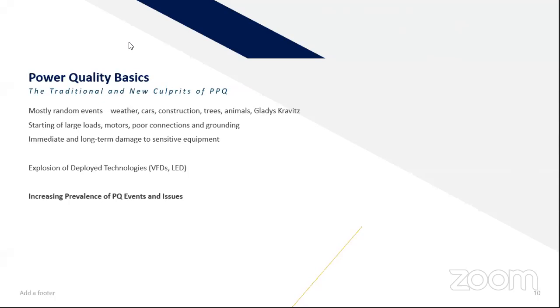Poor connections, everyone knows you've got to torque them to what the manufacturer says. Grounding, like I said, is one of those issues that is incredibly difficult to isolate and to fix, but once you fix it, it's amazing because everything goes away. That's the nice thing about grounding. However, like I said, it's just incredibly difficult to fix.